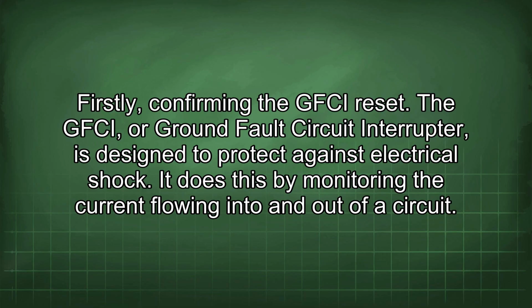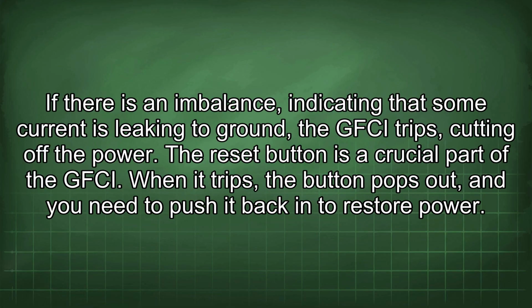Firstly, confirming the GFCI reset. The GFCI, or ground fault circuit interrupter, is designed to protect against electrical shock. It does this by monitoring the current flowing into and out of a circuit. If there is an imbalance, indicating that some current is leaking to ground, the GFCI trips, cutting off the power.